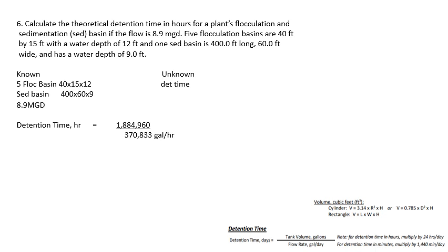Add those together, get a total volume of 1,884,960 gallons divided by 370,833 gallons an hour. That gives you a detention time of 5.1 hours.